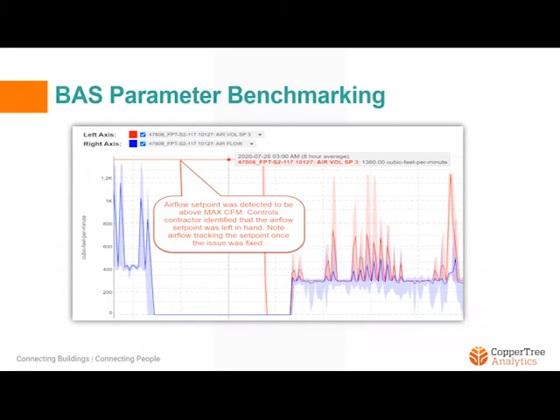Think about the same tool which you can use to catch issues like this. Michael already talked about this, but again, this is a real world example where we noticed that the airflow set point was above max CFM. The controls contractor identified that the airflow set point was left in hand, and once it was fixed, you can see on the right-hand side, the airflow correctly tracking the set point.